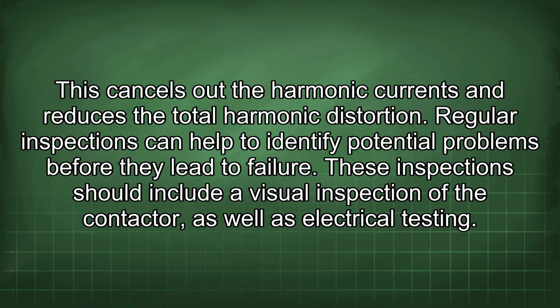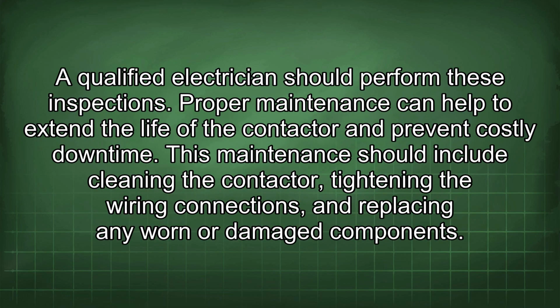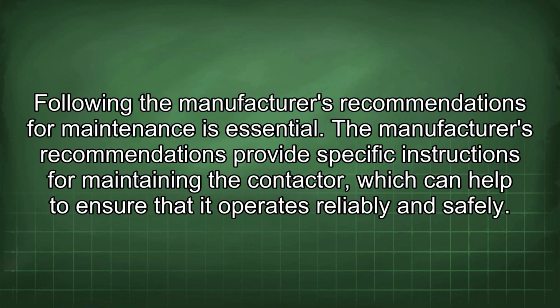Regular inspections can help to identify potential problems before they lead to failure. These inspections should include a visual inspection of the contactor as well as electrical testing. A qualified electrician should perform these inspections. Proper maintenance can help to extend the life of the contactor and prevent costly downtime. This maintenance should include cleaning the contactor, tightening the wiring connections, and replacing any worn or damaged components. Following the manufacturer's recommendations for maintenance is essential.